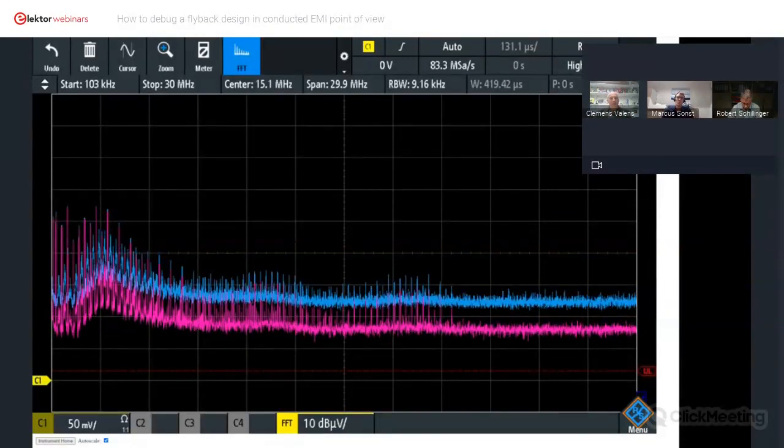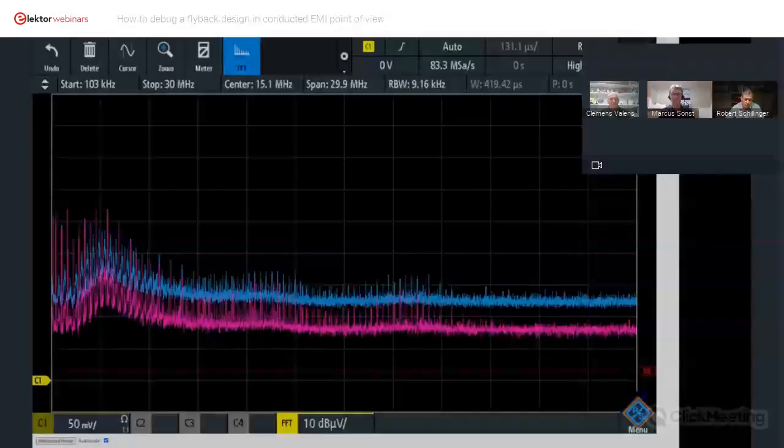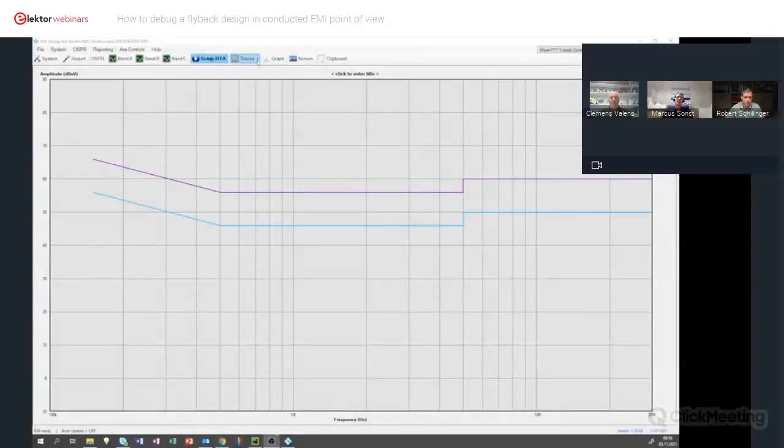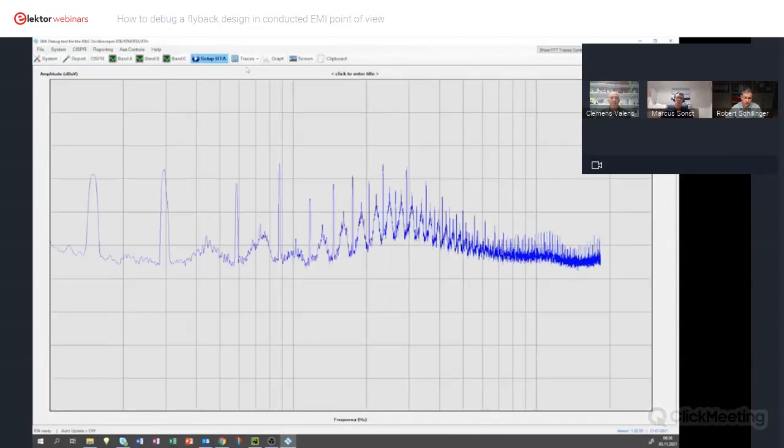And now we are switching back with the camera to the external PC tool in a few seconds. Yes, now we are switching back. And the only thing we then have to do is just ask for the data. So we have to press only one button and ask for the data. The limit lines are already in the main window, and it takes a short moment, depending on how fast the transfer can be, or the link you have used.